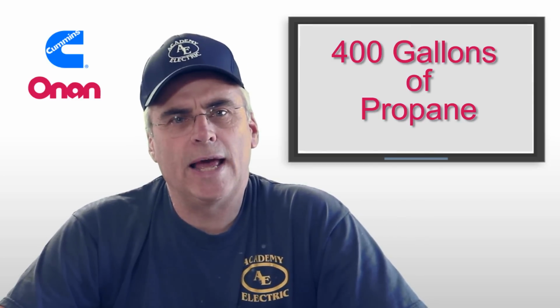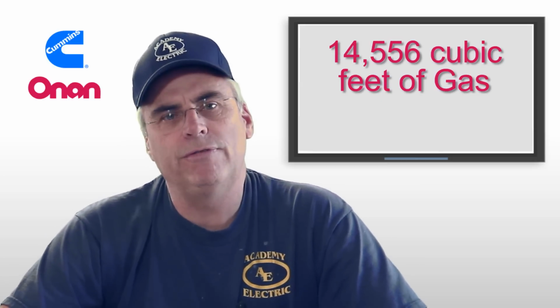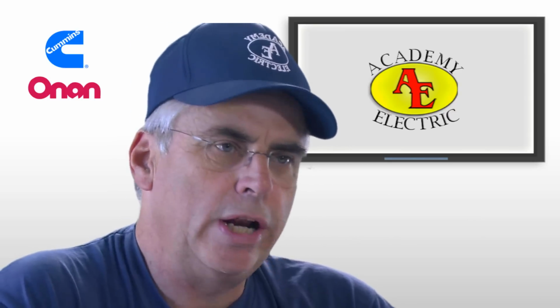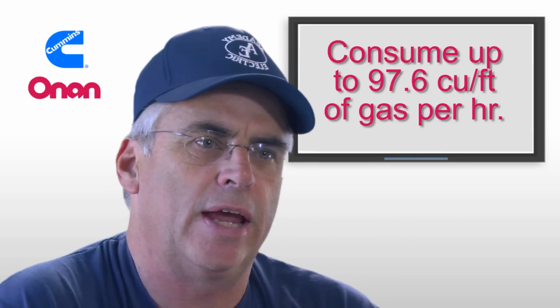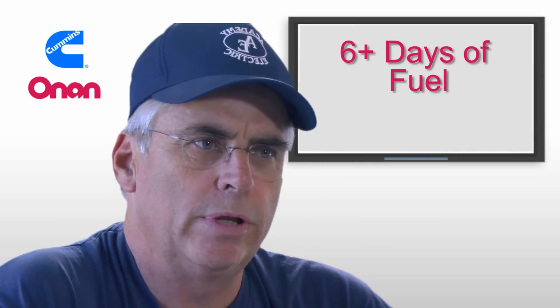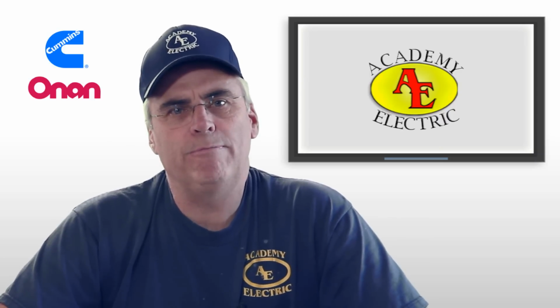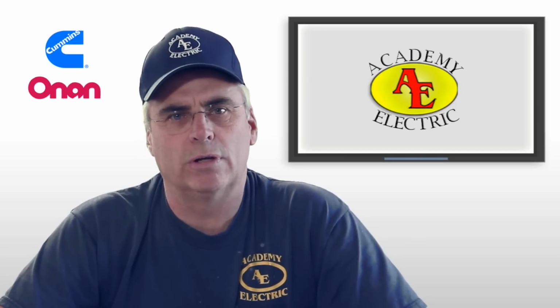So 400 gallons of propane in a tank is 14,556 cubic feet of gas. An RS-20 generator loaded at 3/4 load is going to consume 97.6 cubic feet of gas an hour. That's a little high for an estimate, but again, I'd rather err on the side of caution. That would relate to, at 24 hours a day, 6+ days of fuel that you would have in the ground to run your generator. There's never been a time where we've been completely isolated for 6 days and not able to get a propane truck back to refill the tank.